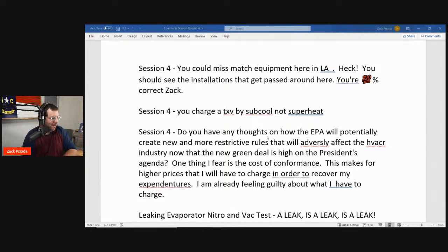The next comment is, you charge a TXV by subcool, not superheat, which is true. You do charge it with subcool to get the proper liquid to the expansion device, but you also monitor superheat to make sure it's in a general range or specified range, depending on what you're putting in. Typically, I think normal is going to be anywhere from 7 degrees or so on the low end.